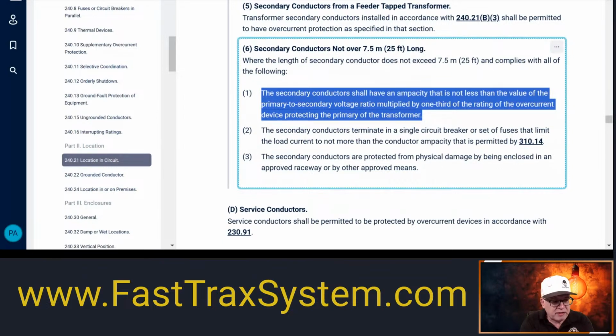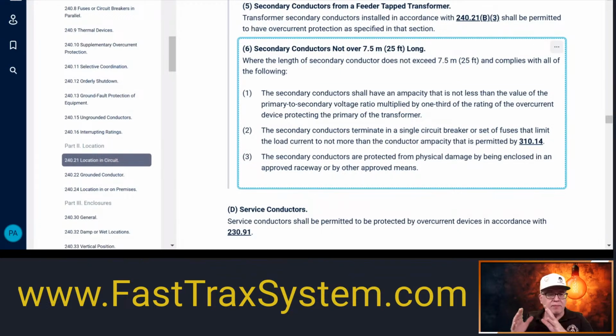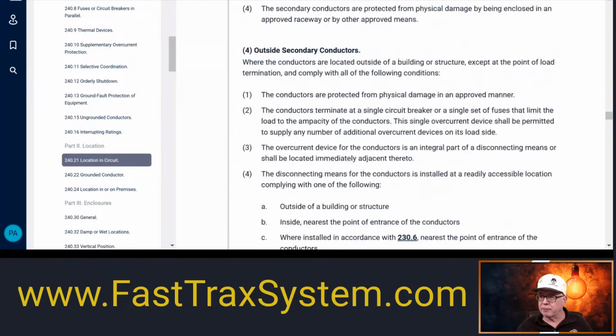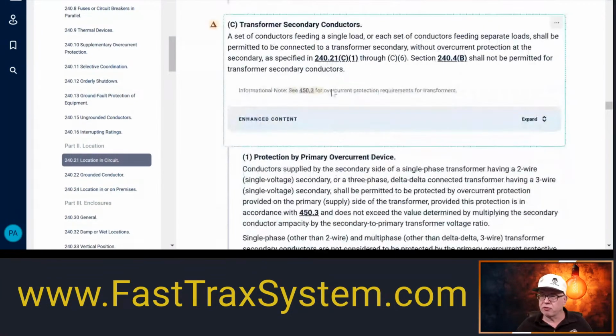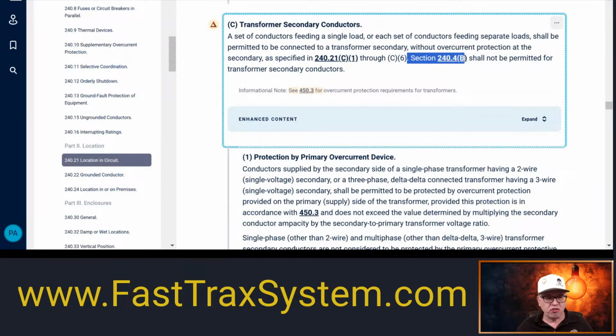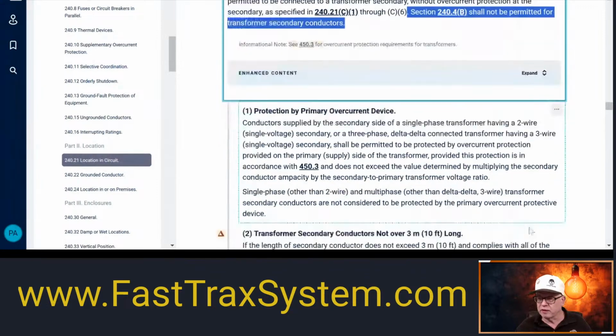Now, for us, we know the chances of finding a conductor that is exactly 96 amps is not going to happen, so we pick a conductor that can at least handle the 96 amps, okay? And then at that point, we're going into the panel, and we have to make sure that overcurrent device is going to be limiting the current to whatever the ampacity is of the conductor, right? Remember now, we're not able to use the next size up rules. Why? Y'all remember what we saw earlier, the general rule, or we saw the other day? When it comes to these transformer secondary rules, it says section 240.4(B) shall not be permitted for transformer secondary conductor. So we can't use a next size up rule for this.